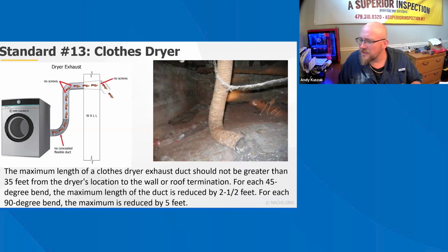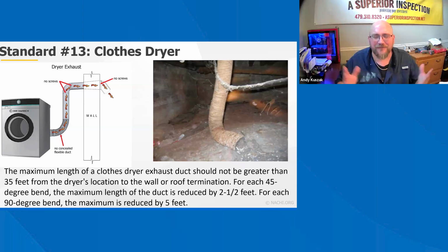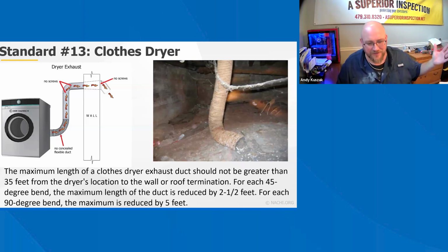Screens, lengths. Lengths are very difficult to evaluate. So, I guess for me, as long as the dryer is on the far side of the house and my dryer vent is on the opposite side of the house, then you've got to start looking for, well, is there any lint even coming out of there? Because of the distance, maybe it's clogged 10 feet back or whatever.